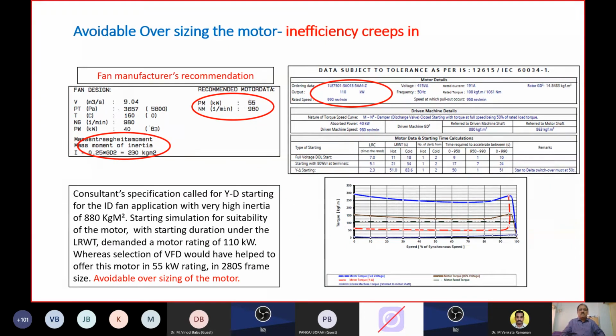Just one slide on oversizing, which happens generally thanks to consultants or contractors. I don't know if you will ever come to this situation in your academic career, but if it does, I can expand with more slides on selection and things like that. I have presented on selection of motors for variable torque load, constant torque load, and material handling applications. So those slides can be made available for some of you who are interested in understanding what variations need to be adopted. But here in this one slide, I am trying to cover that a consultant specification calling for star delta starting for an ID fan application with a very high inertia of the impeller demanded that the 110 kilowatt motor is selected in a larger frame size. The moment you go to a larger frame size, efficiency will come down.